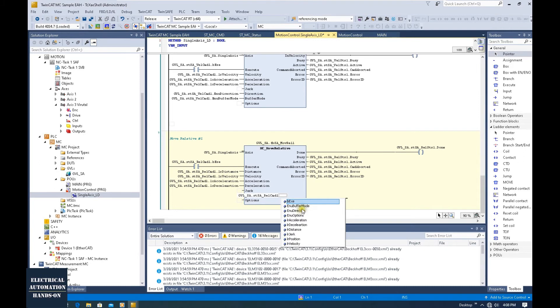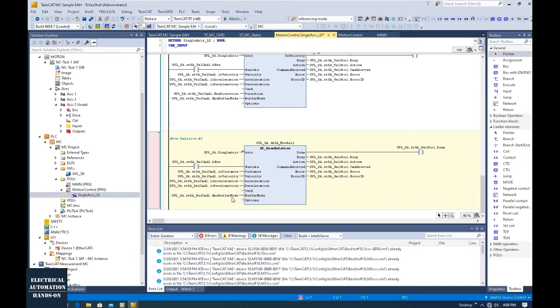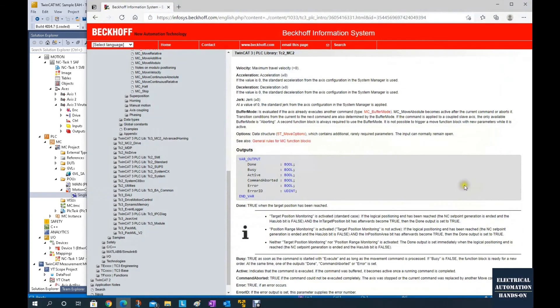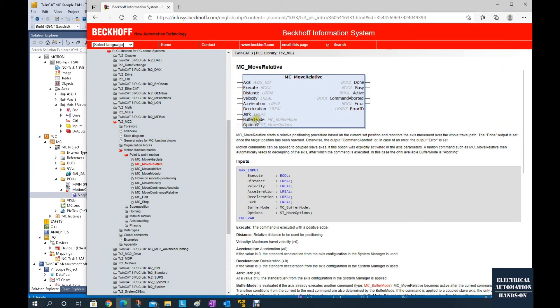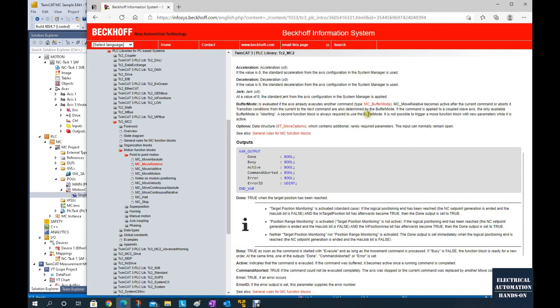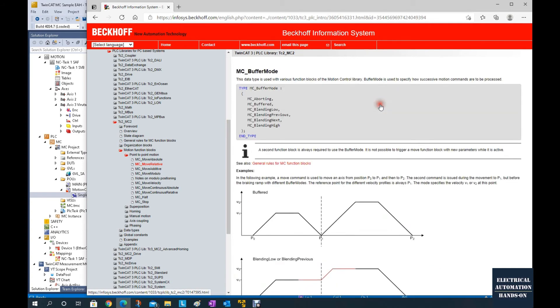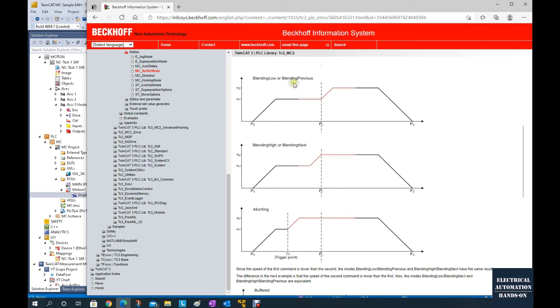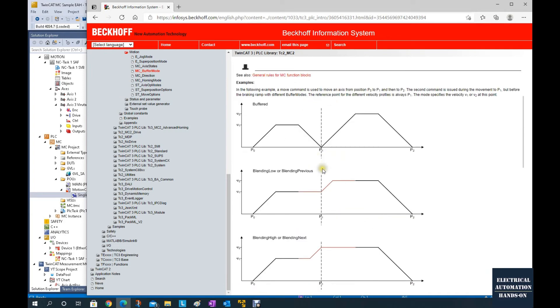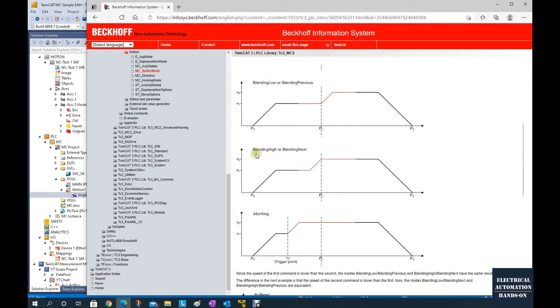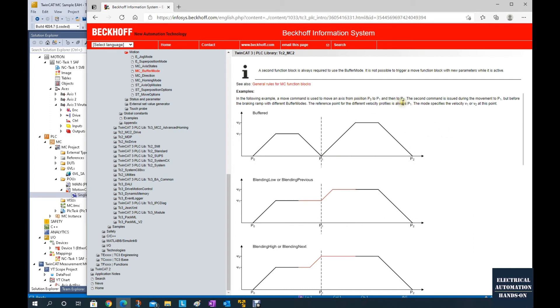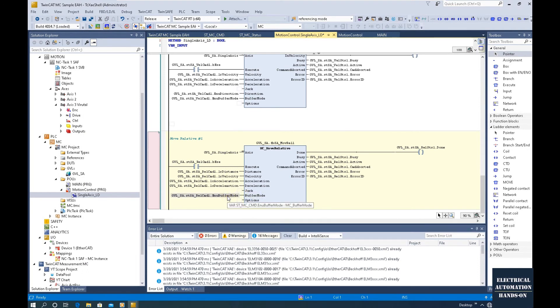For buffer mode, we can select the buffer mode. Regarding buffer mode, if we look at the Infosys documentation for move relative and find buffer mode — buffer mode evaluates what happens if the axis is already executing another command when a new command comes in. Clicking MC_BufferMode, we see clearly from the trend curves the different selections: typical options are 'Buffered' (the default) or 'Blending High'/'Blending Next' where speed can be continuous rather than aborting. It depends entirely on the application.